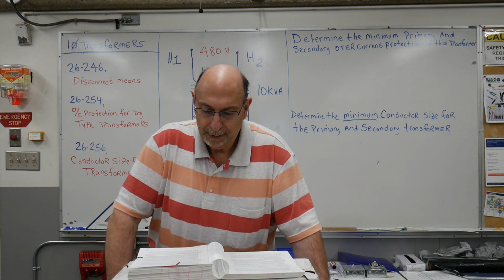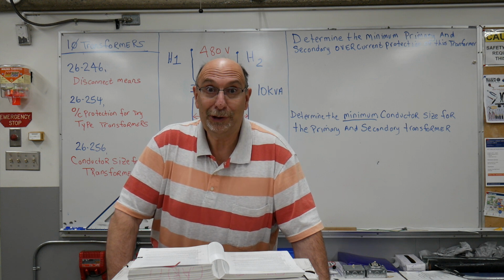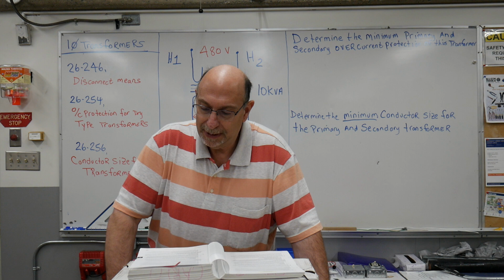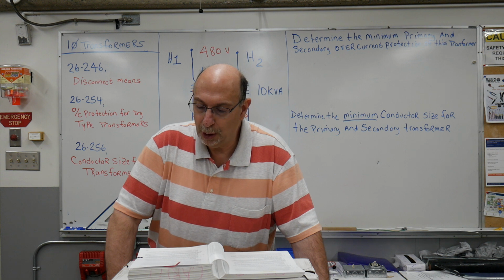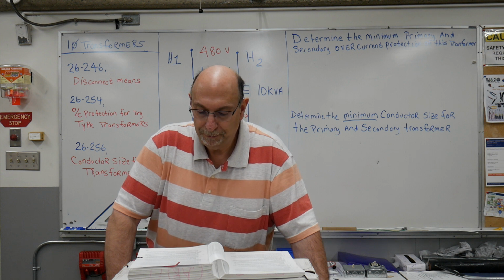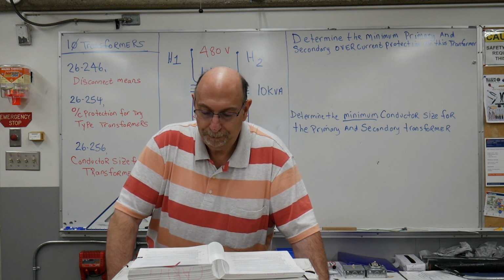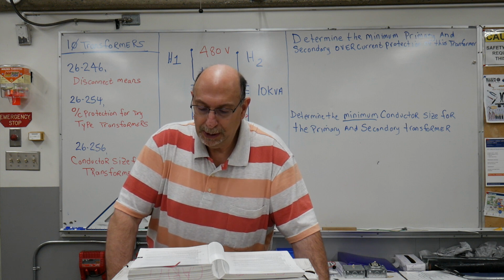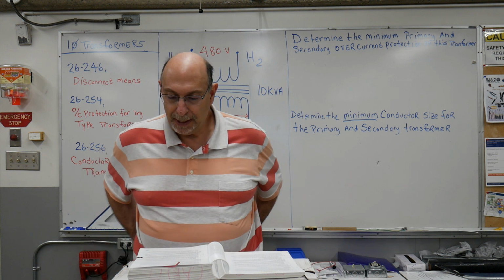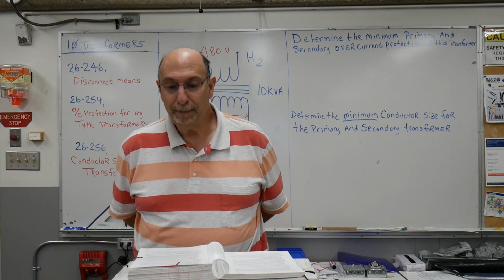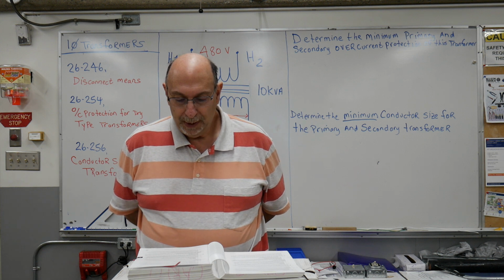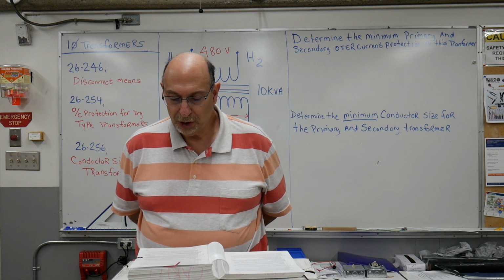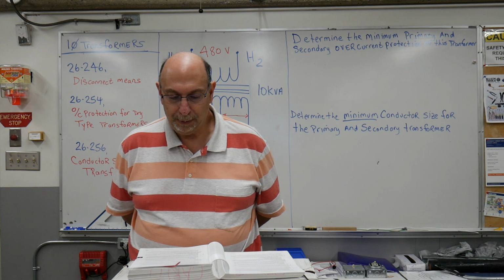And sub-rule 3 says, notwithstanding sub-rule 1, so forget about what we just read, where the adjacent surface is the wall on which the transformer is mounted, the minimum permissible separation between the enclosure and the mounting wall shall be 6 millimeters if the adjacent surface is made of A, non-combustible material, B, combustible material adequately protected by non-combustible heat insulating material other than sheet metal, or sub-rule C, combustible material shielded by grounded sheet metal with an airspace of not less than 50 millimeters between the sheet metal and the combustible material.